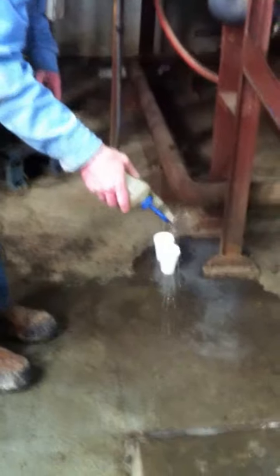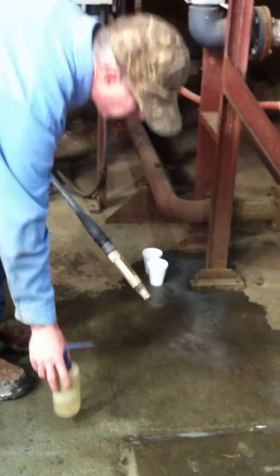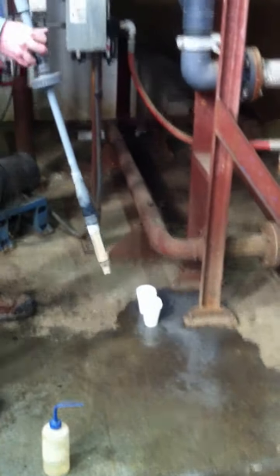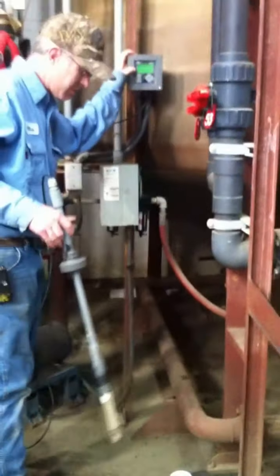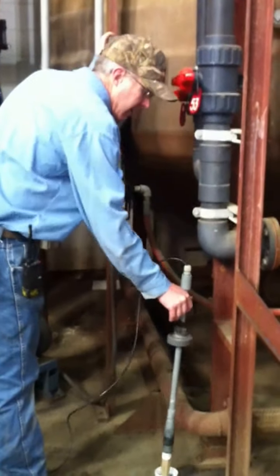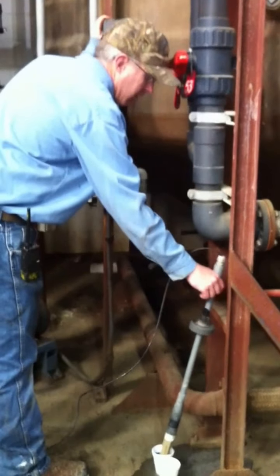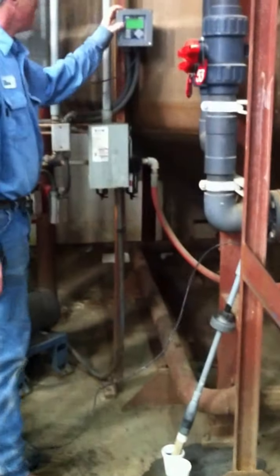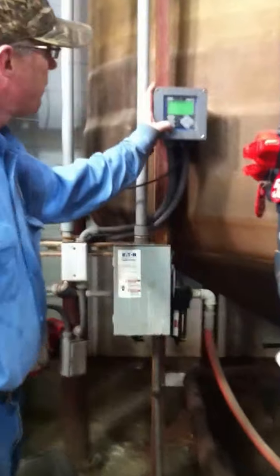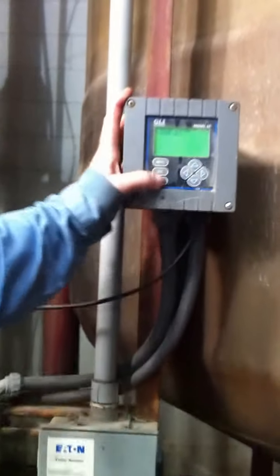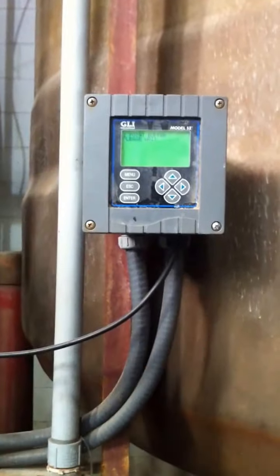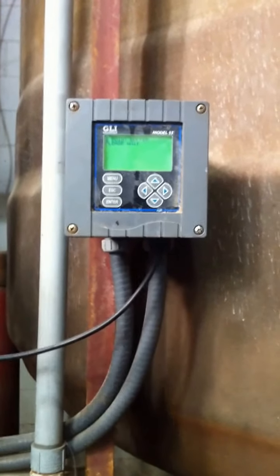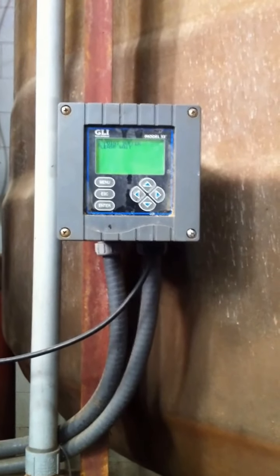At that point, you'll remove your probe from your 7, bring it out, rinse the tip again with deionized water. It's asking now if the buffer's in the second solution. So I'm going to go ahead and put the probe in the 10, lean it back, and then I'm going to press enter on the controller. And after I push enter, it will begin to calibrate to the 10. May take a little bit of time.